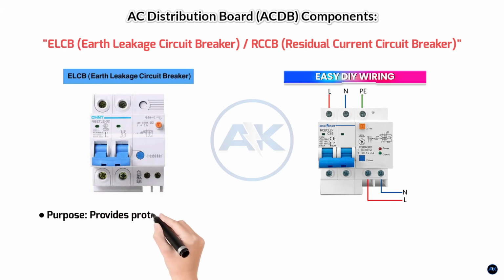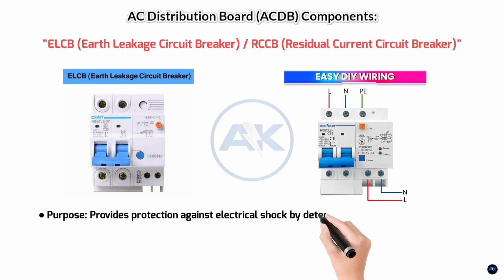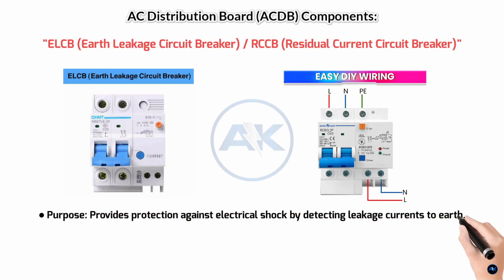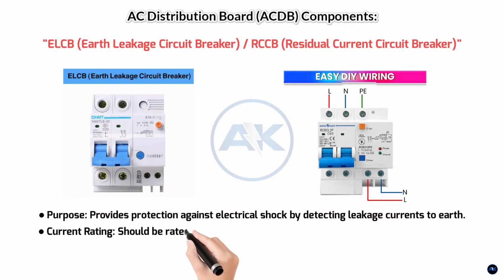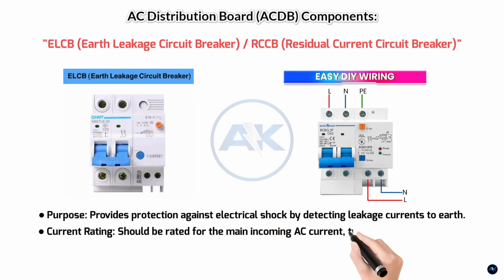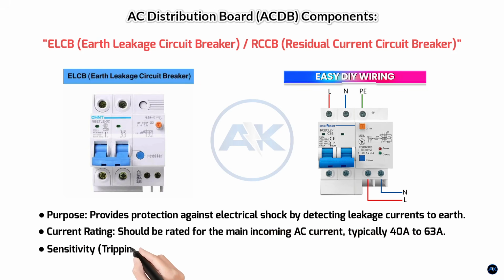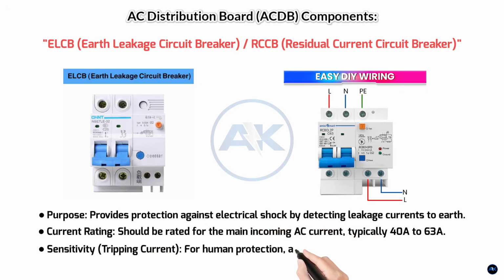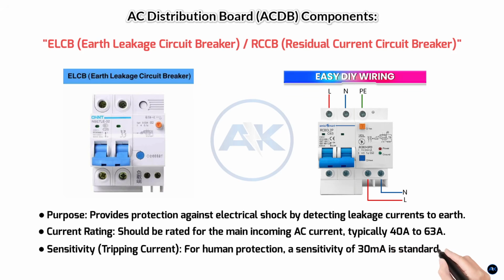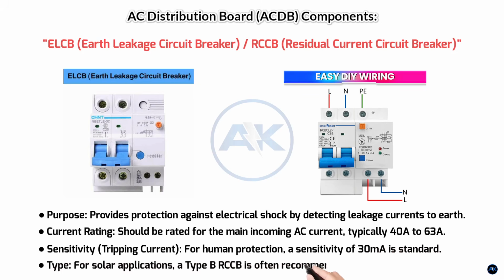Purpose: provides protection against electrical shock by detecting leakage currents to earth. Current rating: should be rated for the main incoming AC current, typically 40 amps to 63 amps. Sensitivity: tripping current. For human protection, a sensitivity of 30 milliamperes is standard. Type: for solar applications, a type B RCCB is often recommended.